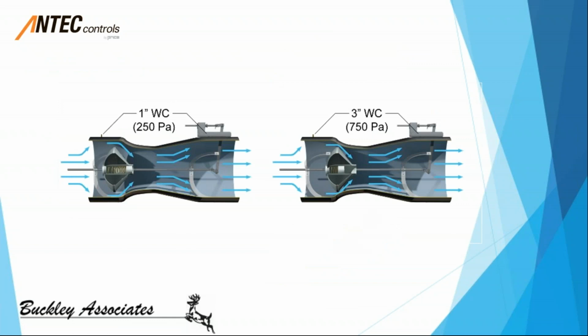So on the left side of the slide here, we see a valve at 1-inch static pressure. This is a relatively low static pressure condition where the spring inside the cone is not compressed very much. Here's a little cut so you can see the spring operating in this. This allows for more space and more airflow to move through the valve. So you can see these orifices on top. As this cone is further towards the inlet of this valve, there's more space around the cone for air to flow.